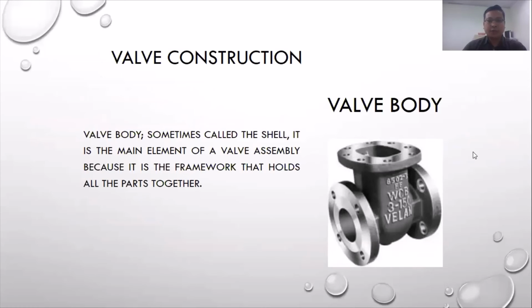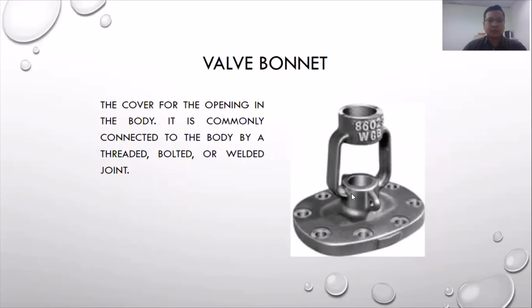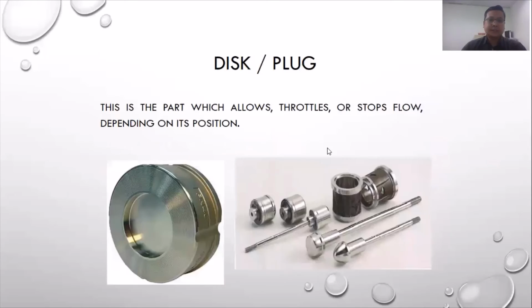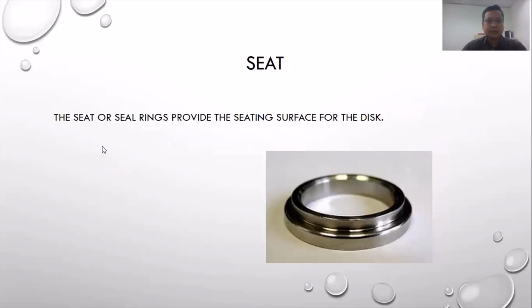Okay, this one is the body of the valve. You can see this is like the casing of the valve with the inlet and outlet, and the top one is for controlling. Inside the body there is the plug. Also, we have a seat or ring inside to avoid leakage from the piping system or valve system.